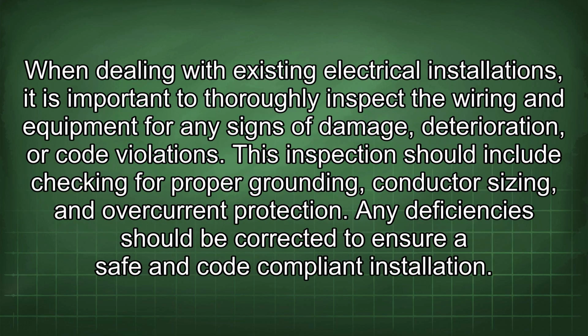When dealing with existing electrical installations, it is important to thoroughly inspect the wiring and equipment for any signs of damage, deterioration, or code violations. This inspection should include checking for proper grounding, conductor sizing, and overcurrent protection. Any deficiencies should be corrected to ensure a safe and code-compliant installation.